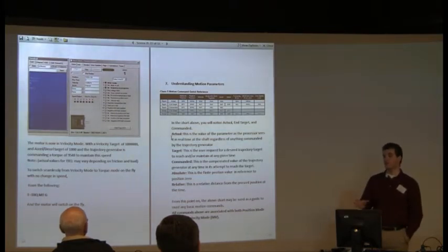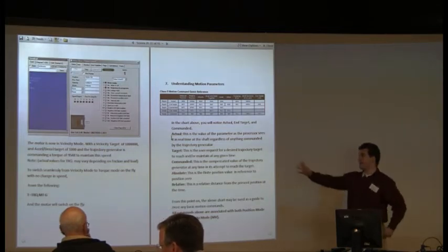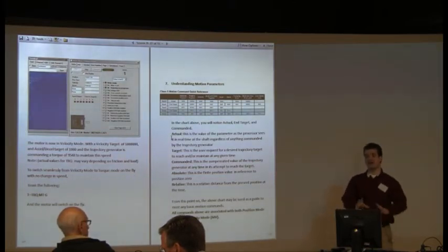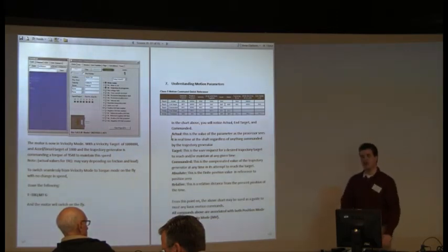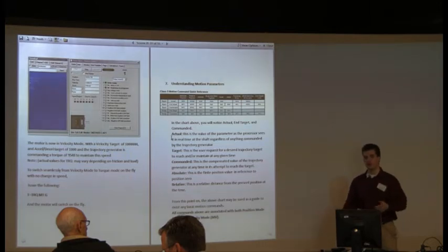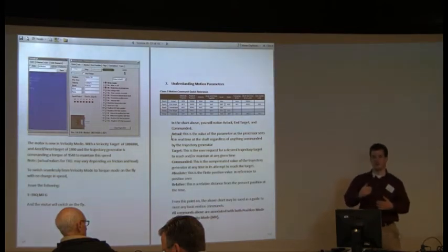That 9548 was just what we happened to observe as it was making that velocity move. Yours might be a little bit different. That torque is going to depend on wind resistance, resistance in the bearings, anything like that. It's trying to maintain that particular velocity of one million regardless of how much torque is being applied to the shaft. So if you're doing a velocity move and you try to stop the shaft, the motor will apply more torque to that to keep the move the same. But once we transition to torque move, it doesn't care. It's going to maintain the same torque regardless of speed. Or just say the same percentage of PWM in regards to speed. At no load, it's obviously exerting no torque beyond what it takes to overcome the friction, the bearings and things like that. As is the nature of a permanent magnet motor.